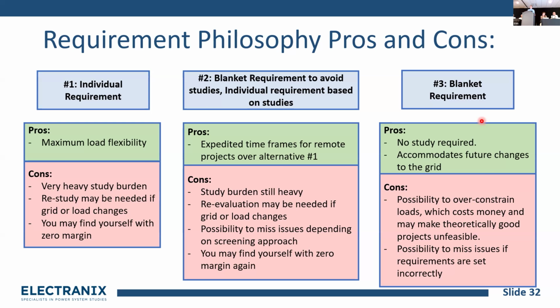If you go to a blanket requirement with exceptions, you can quickly accelerate load interconnections if folks are compliant. So if people are meeting your requirement, you can relatively quickly connect loads without doing a study. The downside is the study burden is still heavy because many loads early on won't be able to meet that requirement, since it's probably going to be narrow. You will also have to reevaluate if things change.